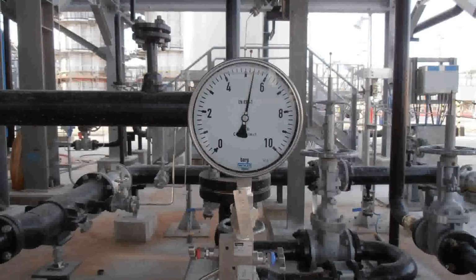Class of the instrument is absolute error of measurement expressed as percentage of instrument range. For example, if a pressure gauge has the range of 0 to 10 bar and the class of 1, its absolute error of measurement is 1% of 10 bar equals 0,1 bar. Absolute error is the same on the whole range. Relative and percentage errors are smallest at the end of range and the greatest at the beginning of range.